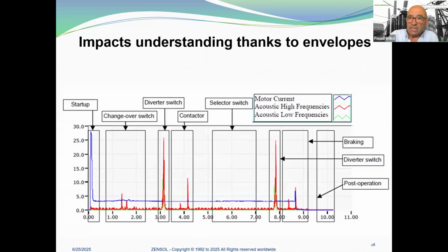Every tap changer has a specific sequence of operations that can be identified in the envelopes. Depending on the model of OLTC, different signatures can be obtained, which are characterized by specific operation length, number of impacts, amplitude of the impacts, shape of the current, and so on.